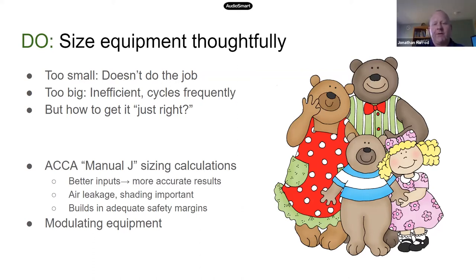Now, most of the heat pumps that we're going to be installing are modulating, which means that they can vary their output across a certain range. So what we want to do is size the system so that on the coldest day we're likely to experience, the system is running pretty much flat out at maximum capacity. But the lower it can modulate down, the more efficient it's going to be in mild weather when we don't need that full capacity. So when we're picking out equipment, we want to first pick the right maximum output, but then within that, look for ones that have a nice wide range of modulation.